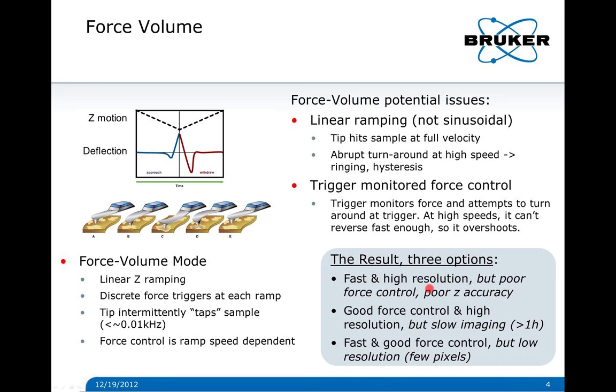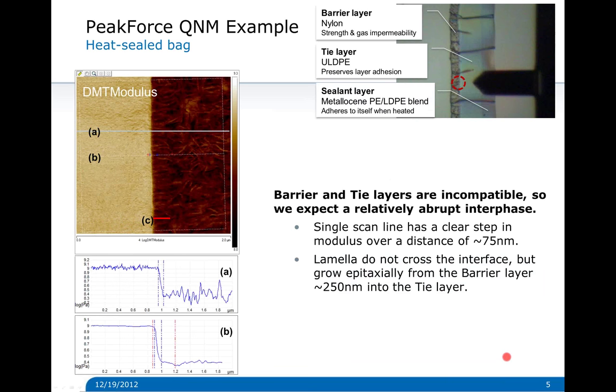These are mainly issues with high-speed force volume. At lower speeds you're fine. But basically it results in three options: go fast with relatively high resolution but poor force control and accuracy; have good force control and high resolution but it takes forever; or go fairly fast to collect an image in a reasonable time with good control but without high resolution. Force volume is a useful technique, but peak force is much better if you're trying to get high resolution images in a reasonable amount of time.